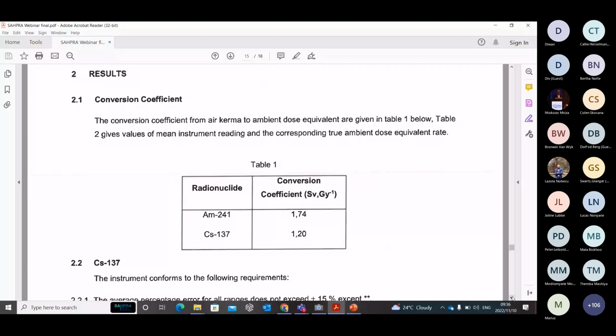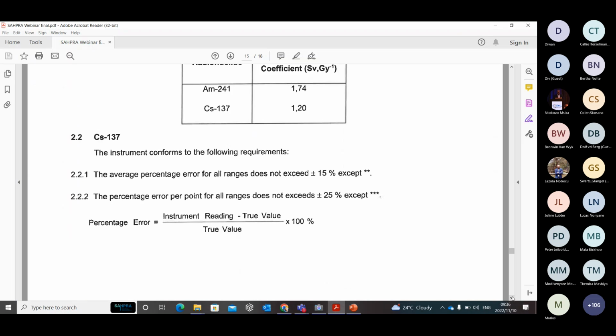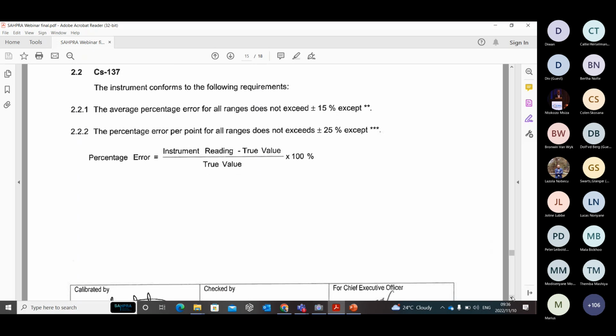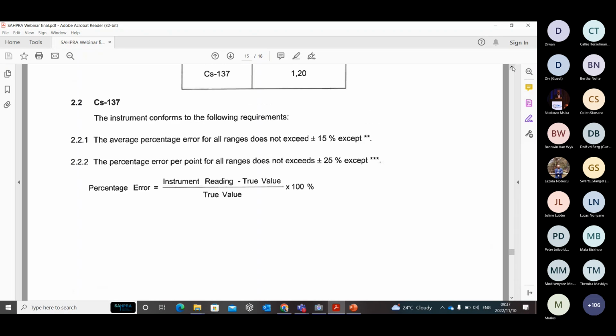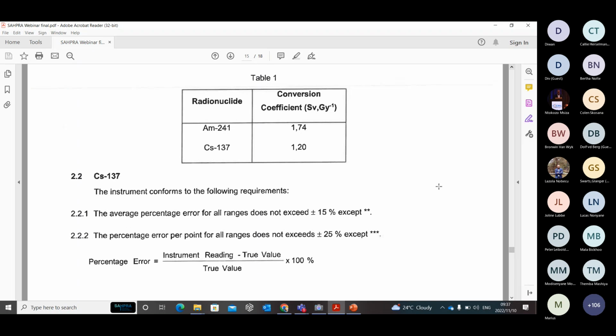In this case, we're looking at the calibration of a survey meter that was calibrated not in air kerma, but in ambient dose equivalent rate, which is an operational quantity that was derived from the air kerma by means of the conversion coefficients as shown in the table for different radionuclides. For example, when we use cesium, we have a conversion coefficient of 1.20. And for americium, which we use only for the energy dependence, we have a conversion coefficient of 1.74.